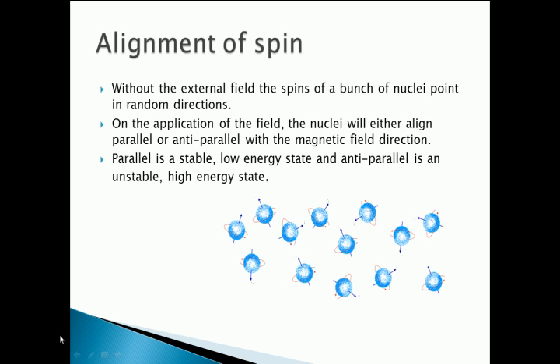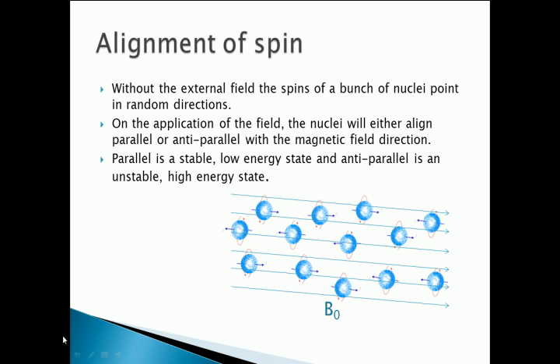That's just one proton. Looking at a whole collection of protons, we can see they have random spin directions to start with. When you apply the magnetic field, they align in the direction of the field. But if you look closely, some have aligned in the parallel direction and others in the anti-parallel direction — they've fallen into two energy states. The parallel state, where the spin vector points in the same direction as the magnetic field, is a low energy state. The anti-parallel direction, pointing opposite to the magnetic field, is a higher energy state. The parallel state is much more stable than the anti-parallel state.